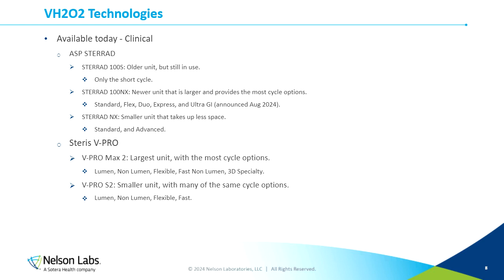So this is an older unit. It is older technology, but because it is older, it has quite a lot of availability around the world, and it's still in use. One of the downsides to the STERRAD 100S is that currently, particularly for the United States, the only cycle option that is available and recognized is the short cycle. So if you're contacting us and you want to validate for the 100S, your only option is the short cycle, and you'll have to make sure that your product fits into that particular cycle. And there are certainly limitations on that cycle, such as lumen size and lumen length, that you would have to review and ensure it's an option.